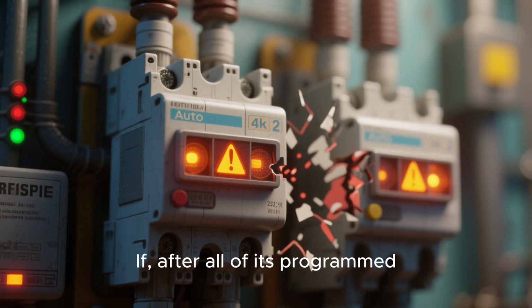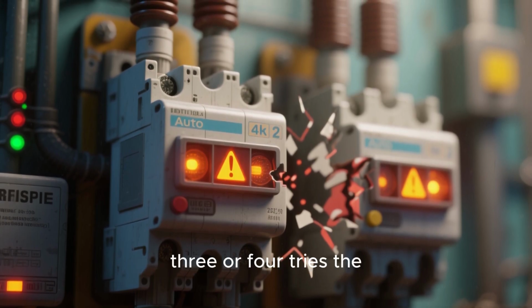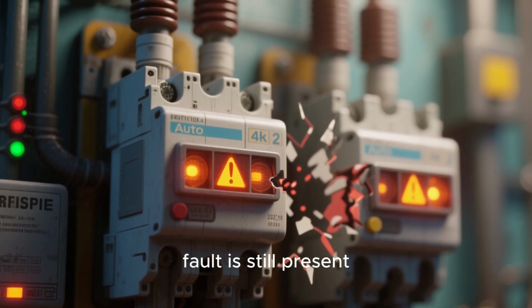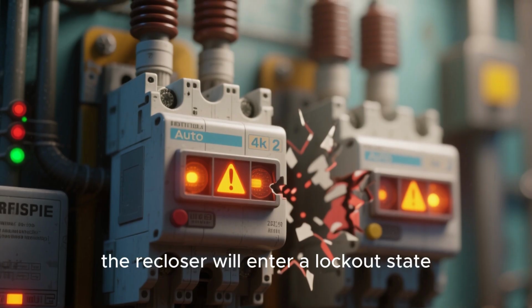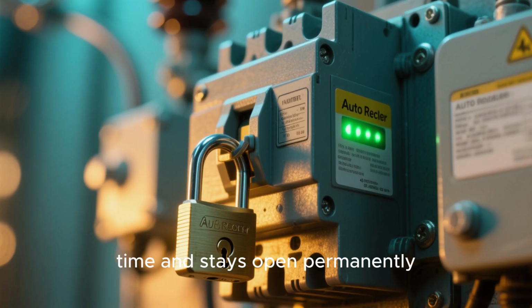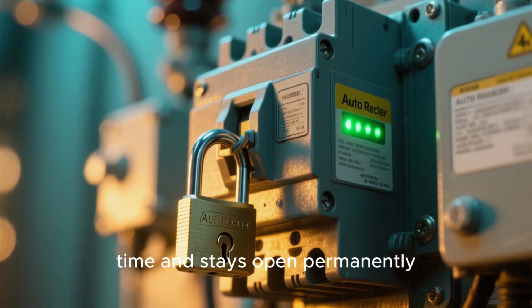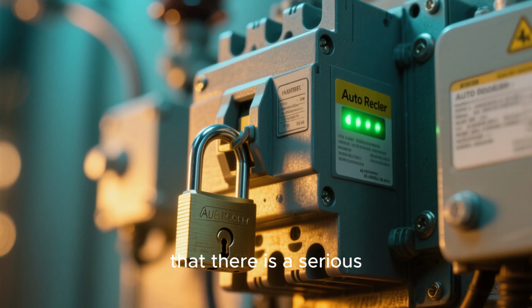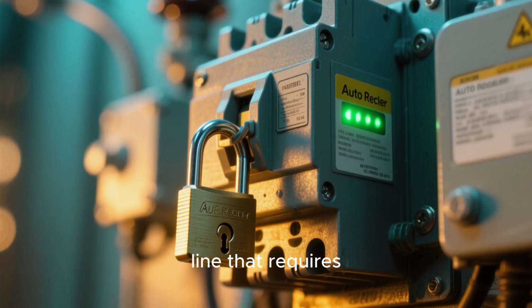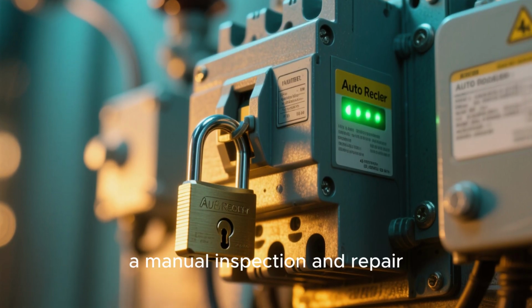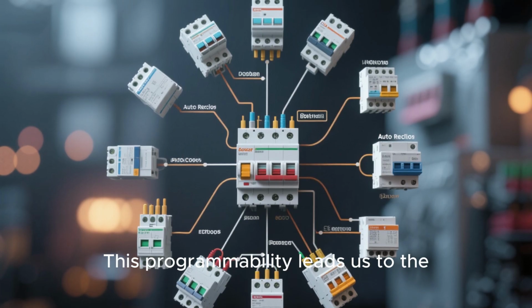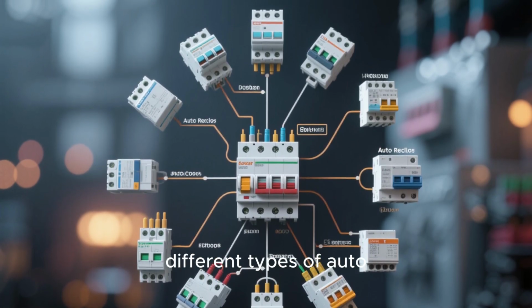If, after all of its programmed attempts, say, 3 or 4 tries, the fault is still present, the recloser will enter a lockout state. It trips one final time and stays open permanently, signaling to the utility that there is a serious, permanent fault on the line that requires a manual inspection and repair. This programmability leads us to the different types of auto reclosers.